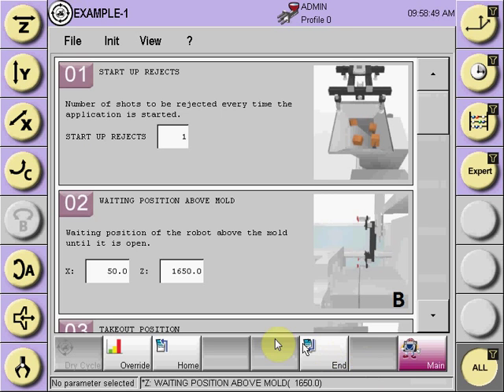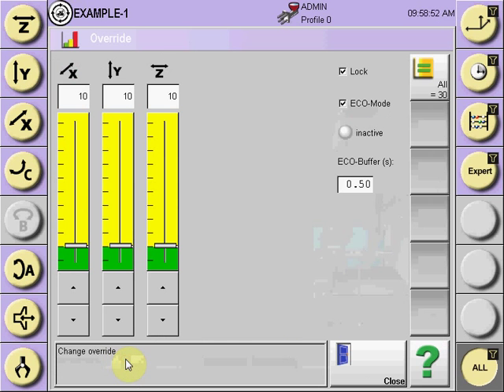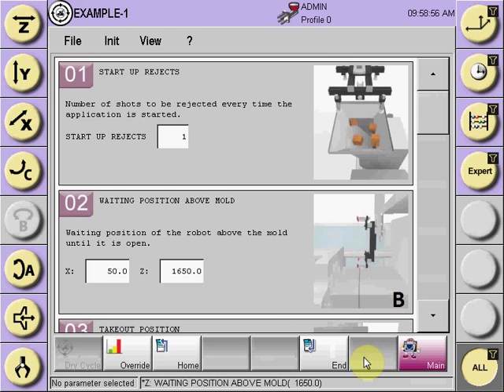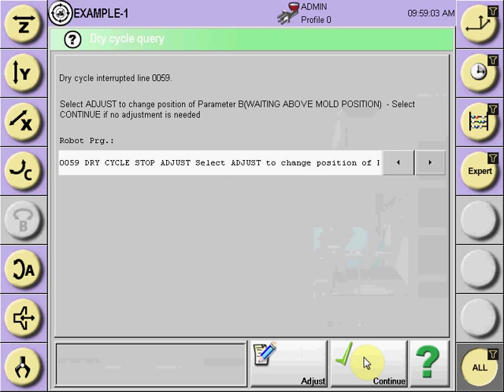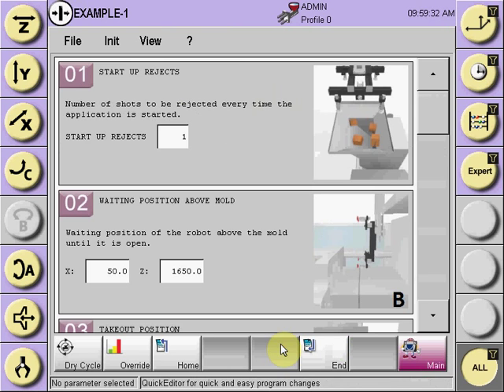The robot will move to the position with the override set at 10%. When it reaches the first position to be evaluated, a dry cycle interrupt appears asking you to select adjust — the lower key on the bottom — to change the position of parameter B, which is the waiting above mold position, or select continue if no adjustment is needed. To evaluate this position, the robot has moved to the above mold position. If an adjustment is needed, select adjust.